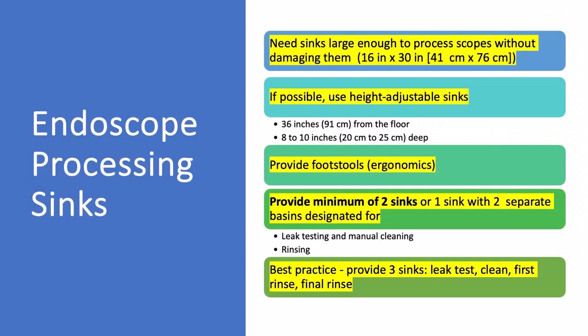Endoscope processing sinks. It's amazing to me. I go into facilities and the sinks, you could just about wash your hands in them. You need sinks that are large enough to process scopes without damaging them, at least 16 by 30 inches. If possible, and you're getting a new area, look at height adjustable sinks because that eliminates a lot of back fatigue. Or you can provide footstools for good ergonomics.